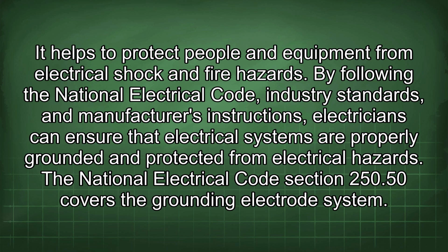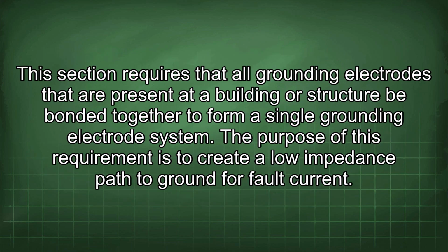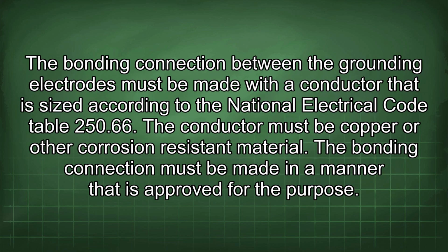The National Electrical Code Section 250.50 covers the grounding electrode system. This section requires that all grounding electrodes that are present at a building or structure be bonded together to form a single grounding electrode system. The purpose of this requirement is to create a low impedance path to ground for fault current. The bonding connection between the grounding electrodes must be made with a conductor that is sized according to the National Electrical Code Table 250.66. The conductor must be copper or other corrosion-resistant material. The bonding connection must be made in a manner that is approved for the purpose.